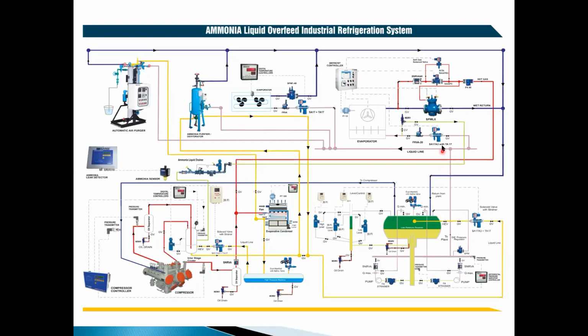When we want to implement hot gas defrosting, we'll cut off the liquid feed, keep running the plant for some time, and let the liquid ammonia in the evaporator get evaporated and fed back into the pump vessel. Then you close the valve in the return line. You start the hot gas solenoid valve. Hot gas will come into the evaporator.